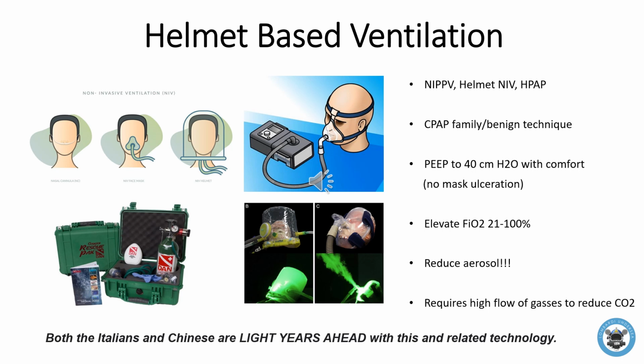But the fact that it can deliver higher pressures comfortably is the key here. So when doing pressure type support with a mask, one complication is ulceration around the face, because you have to wrench down the straps on the mask so tight to get a good fit. So with the helmet, it seals comfortably at the neck and allows pressure delivery quite comfortably. Because it creates this space or chamber, we're able to titrate in supplemental oxygen and control the fraction of oxygen delivered between 21 and 100%.